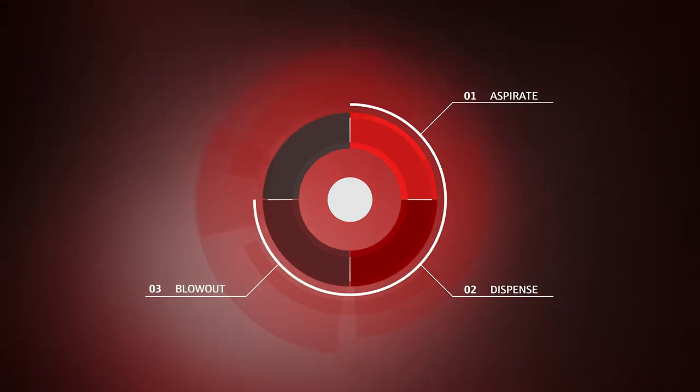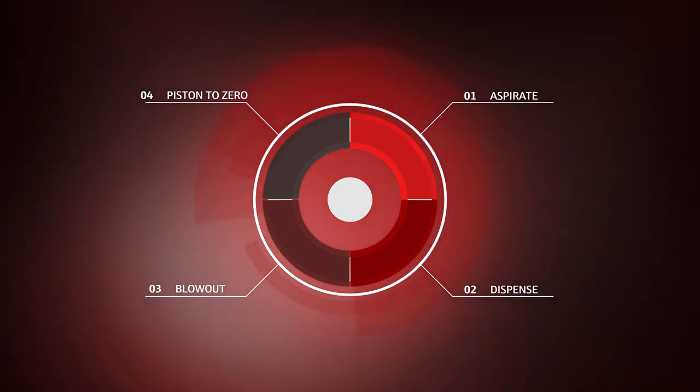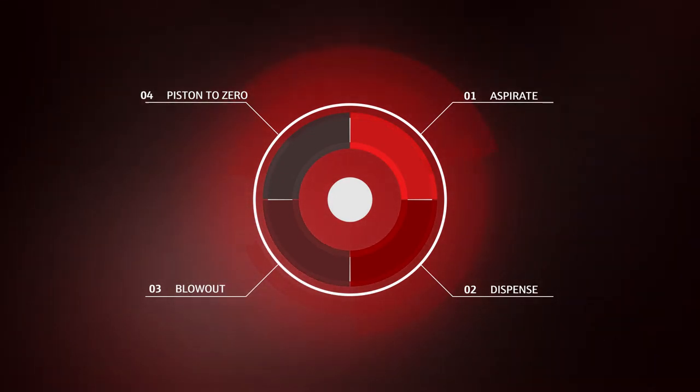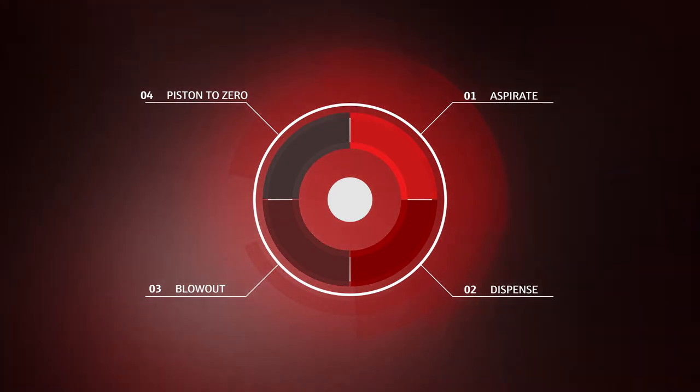The general piston cycle consists of four steps: aspirate, dispense, blowout, and move pistons to zero. When the piston cycle is completed, the piston is back in the starting position and ready for a new liquid transfer.